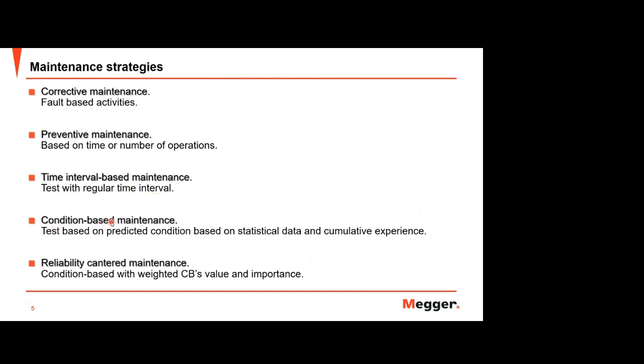And now the next strategy is condition-based maintenance. This is now getting popular in some countries, with some customers. They do testing based on the predicted condition, based on statistical data and cumulative experience. So they don't do regular time interval maintenance, but they just see the condition of the asset based on, maybe, online data. So from the online or monitoring data that they have, they can analyze which part or which asset should continue to the next conventional maintenance. So this is more or less on the monitoring system. From this condition-based maintenance, they just do simple testing to estimate which asset should be stopped, should be de-energized for the conventional testing method.